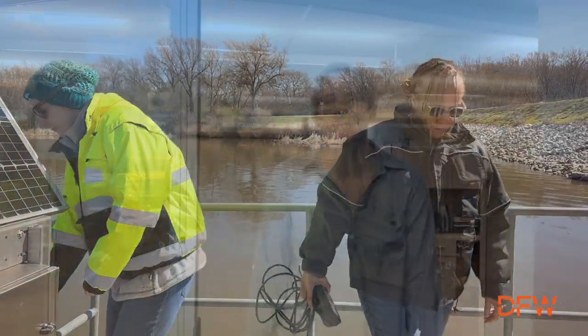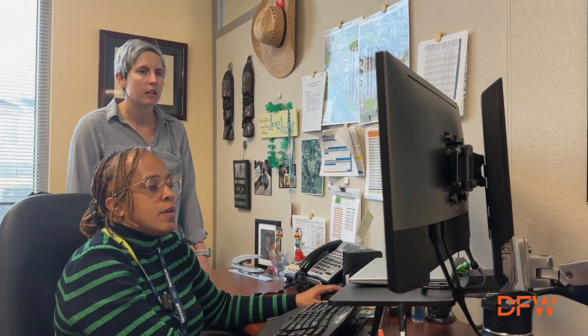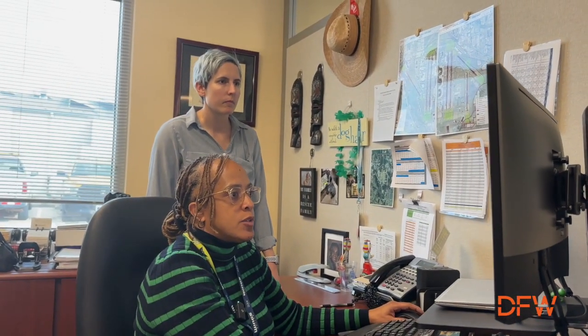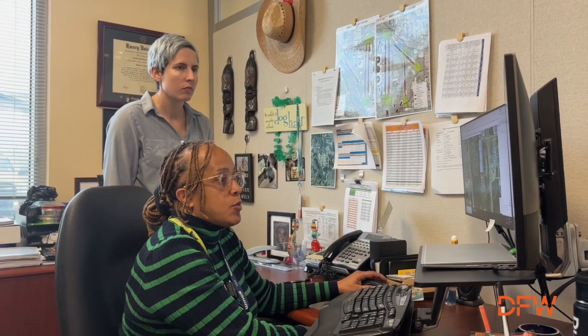All right, thanks. Hey boss, what you up to? Well, I just got back in the office and I wanted to make sure our watershed dashboards were displaying accurate information. Okay. Well, these real-time pages have been extremely beneficial in allowing our team to evaluate water quality trends and notify us when we receive levels that are out of range. You know, earlier today when you were doing the troubleshooting and you had me perform the side-by-side test, it basically proved that the meter in the lake was reading bad information.